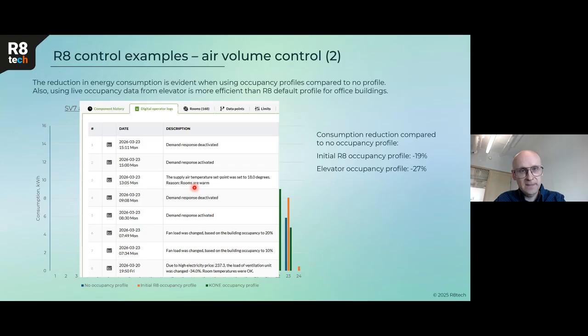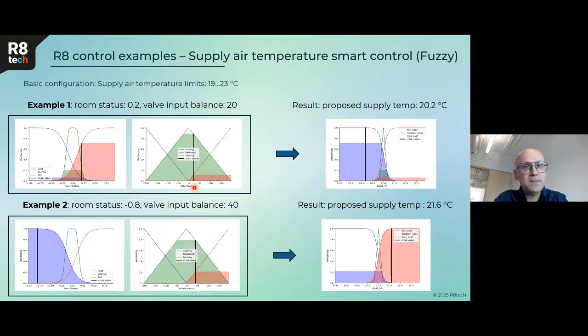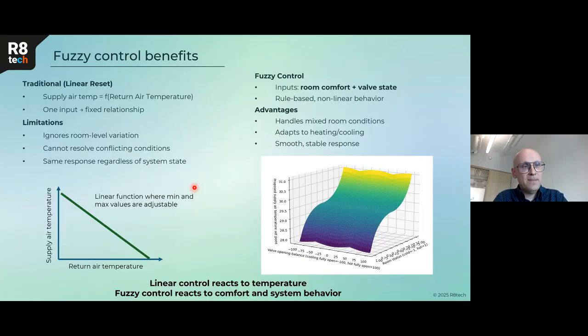And yeah, in our UI, users will see why we did something. For example, the supply temperature smart control. Usually, supply temperature is controlled linearly against the return air temperature, a simple linear function. But we are using fuzzy control, which considers room status for each room. If the room is cold, hot, or okay, it's neutral, it's green. Our goal is to achieve the situation where most rooms are in a green status. Based on that, the fuzzy function will calculate the supply temperature. So in reality, it's smoother and will help to achieve the desired room temperatures.